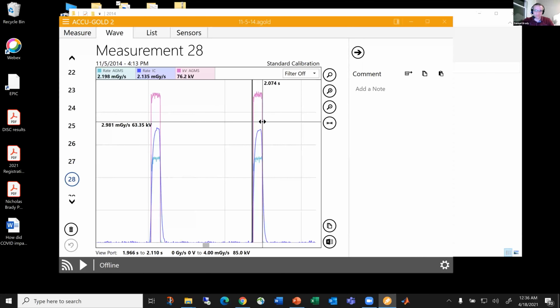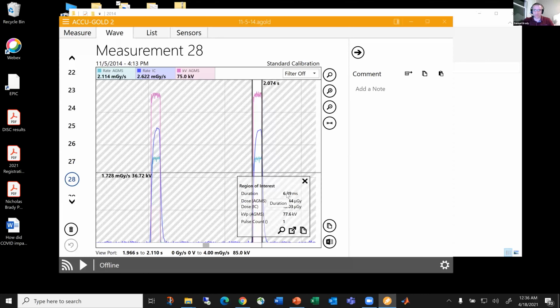See, now you can see the pulse width is almost 6.5 milliseconds. So it had to change that, and for whatever reason, to do it. Now you would think it would actually allow it to go a little smaller, because if it's 15 pulses per second, they're more frequent, so you can actually reduce the amplitude. In this case, they probably reduced the amplitude instead of reducing the width, and so the width had to go wider. That's just a setting in the system that you probably can't change.